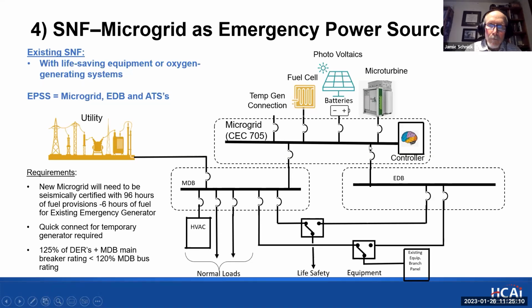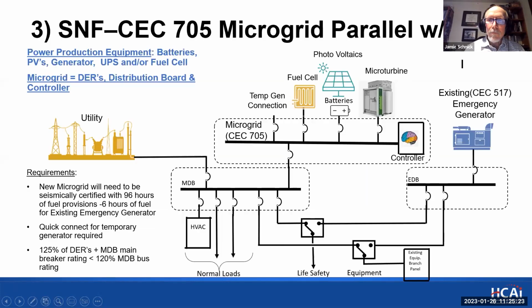The code is very detailed on never the two shall meet except in a transfer switch. That way the system is reliable with redundant pathways, and it would meet all of the requirements. One last thing that I neglected to point out: in the two previous solutions, and this is where we're at today, I wanted to show that last slide of where it could evolve to. But in the two previous solutions, you always had to go back to this generator and make upgrades to meet the 96-hour on-site fuel storage requirement. In this solution, you don't. Why is that? Because you have 96 hours already backing up the entire system. So you meet the requirements of the new law as far as your HVAC and life-saving oxygen generating being backed up for 96 hours, and you meet the requirements of the code for your life safety branch and your equipment branch being backed up for 6 hours.